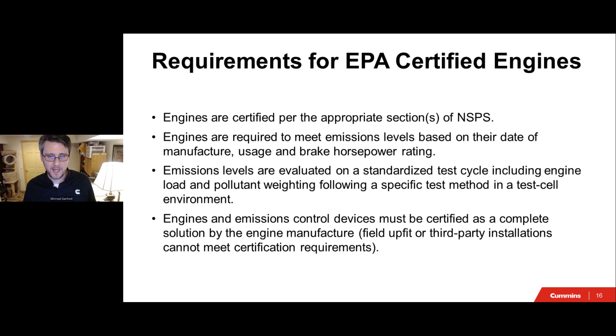And you've got to be careful with the word emergency here because it's often confused for life safety, or maybe a disambiguation with legally required, the NEC 700, 701 loads. There's no alignment between the EPA and NEC, so keep those separate in your mind. The EPA says if the engine or generator set comes on during a failure of the normal source, it is an emergency generator set.